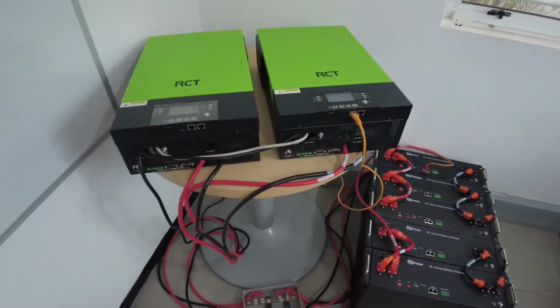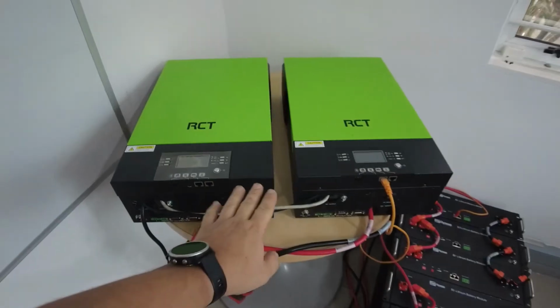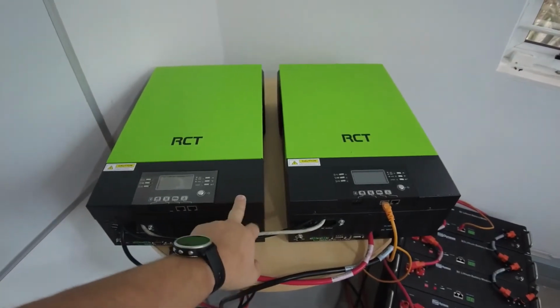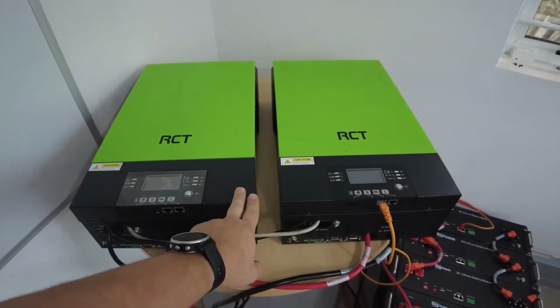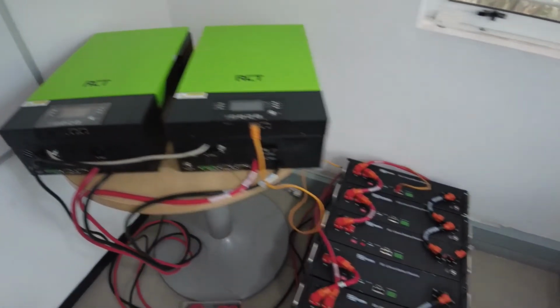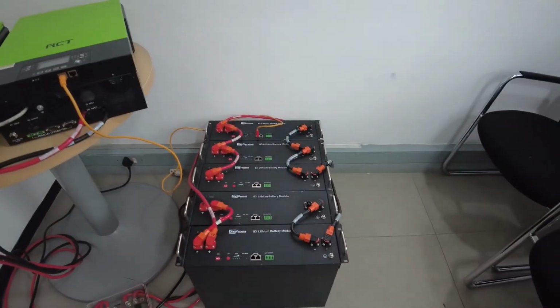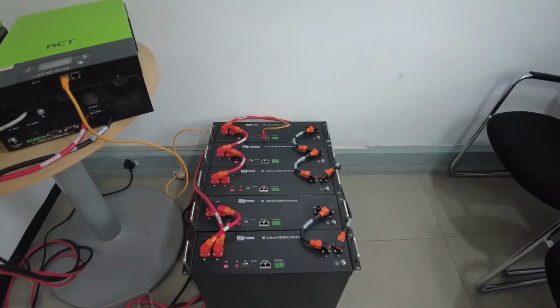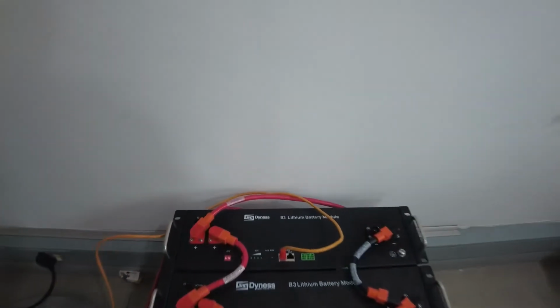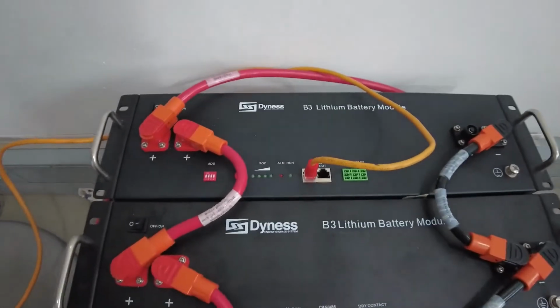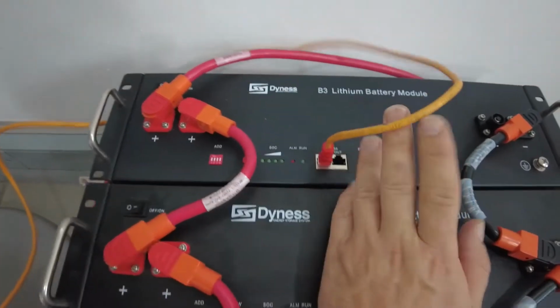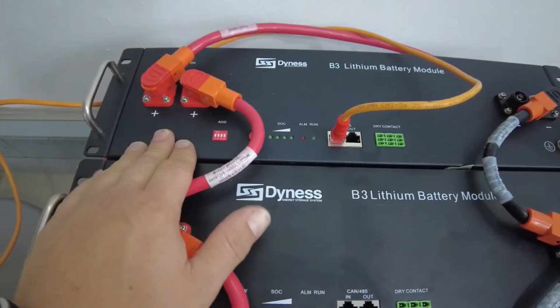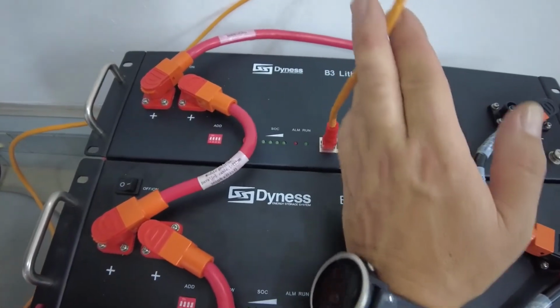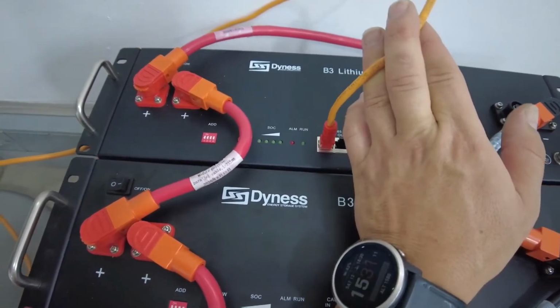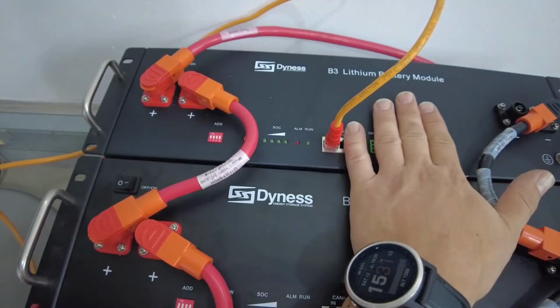Now keep in mind, the first thought you will have is which one of these two inverters is your master, and then obviously which one of these batteries is your master. You will need to set the battery that you connect this cable to as your master. The BMS cable coming from the inverter needs to be connected to the master battery.